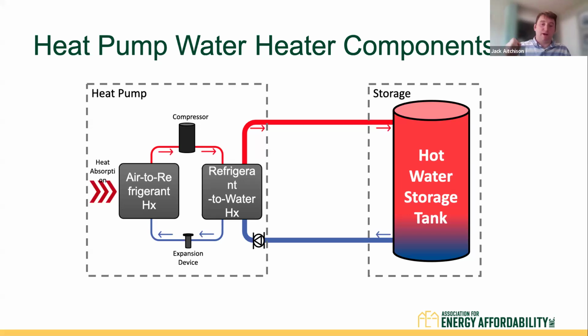It goes through compression, becomes a high pressure superheated vapor, and then it goes through the condenser on the right. Now, the main difference between a heat pump water heater and a heat pump HVAC is the refrigerant to water heat exchanger. Instead of rejecting that heat into the space to heat the area, that refrigerant to water heat exchanger is rejecting the heat into the water, and that is how it heats water.